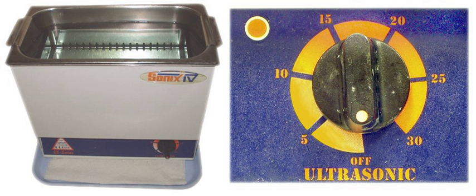Topic: Cleaning solution. Ultrasonic activity cavitation helps the solution to do its job. Plain water would not normally be effective. The cleaning solution contains ingredients designed to make ultrasonic cleaning more effective. For example, reduction of surface tension increases cavitation levels, so the solution contains a good wetting agent, surfactant. Aqueous cleaning solutions contain detergents, wetting agents and other components, and have a large influence on the cleaning process. Correct composition of the solution is very dependent upon the item cleaned.